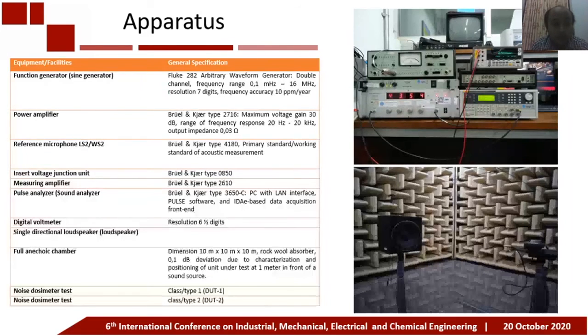And this is the apparatus that supports the calibration of noise dosimeter. This is the control room, containing the signal generator, power amplifier, conditioning amplifier, and sound analyzer. Meanwhile, inside the full anechoic chamber, there are a loudspeaker and a microphone and or a noise dosimeter. In this research we use two noise dosimeters based on their grade: class 1, which we later call DUT1, and class 2, or DUT2.